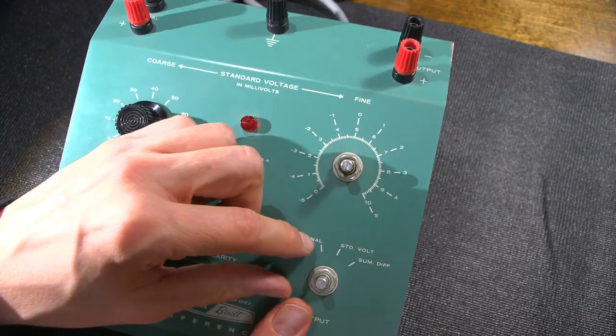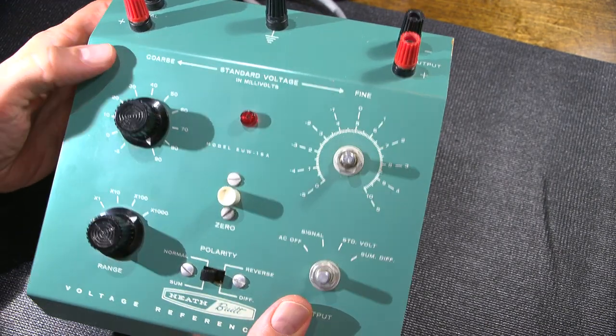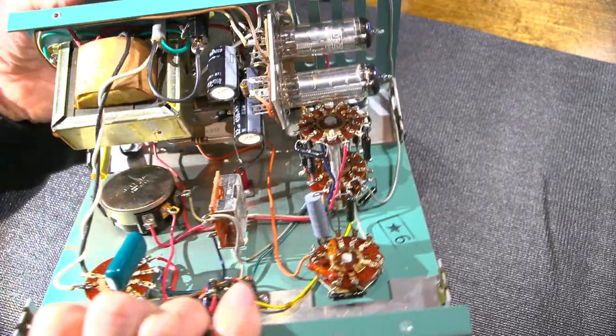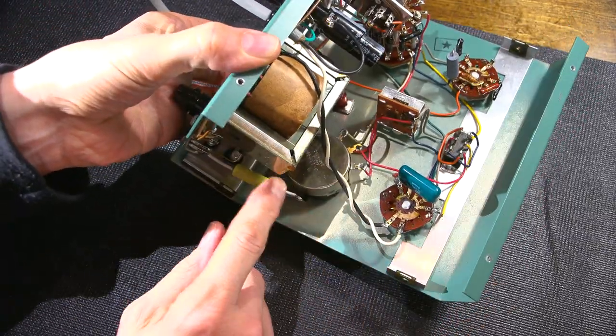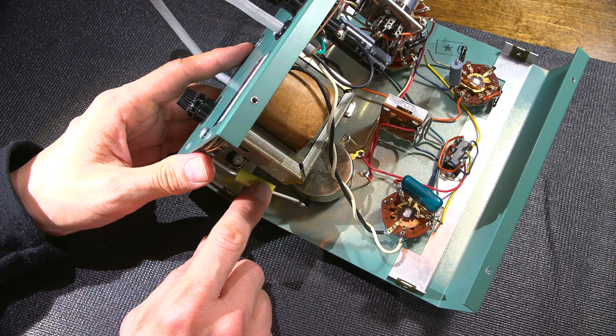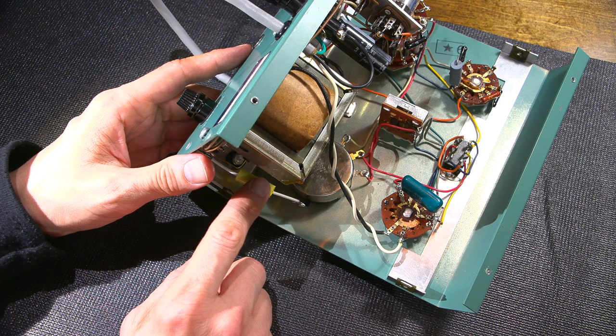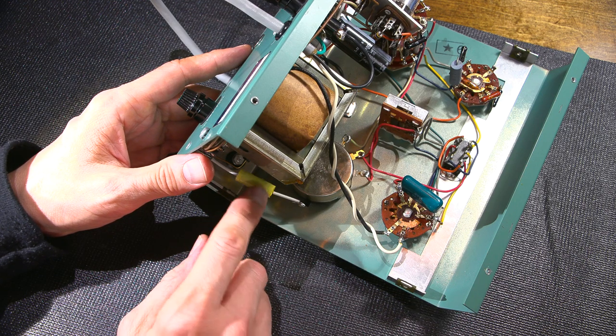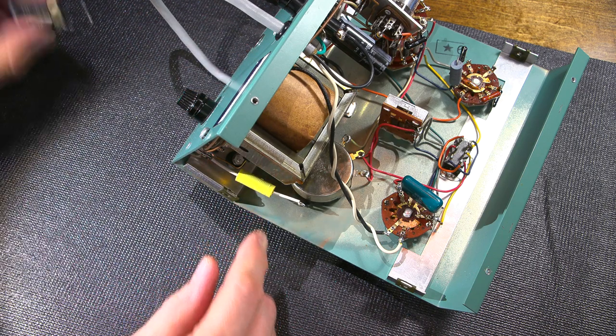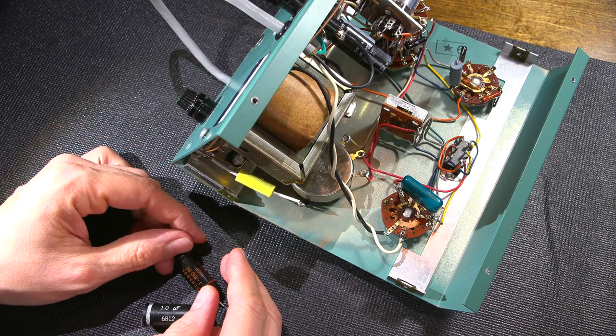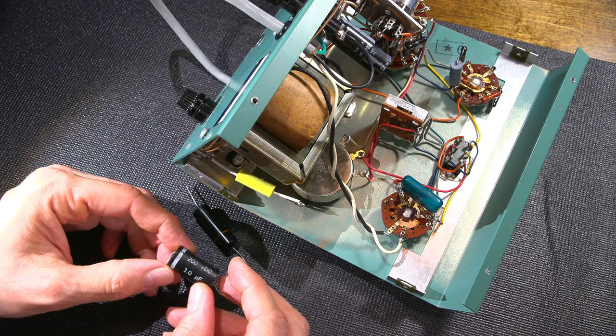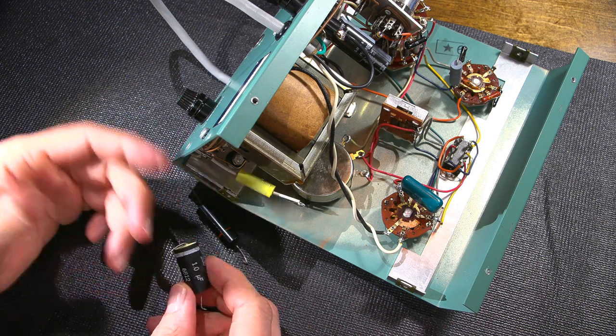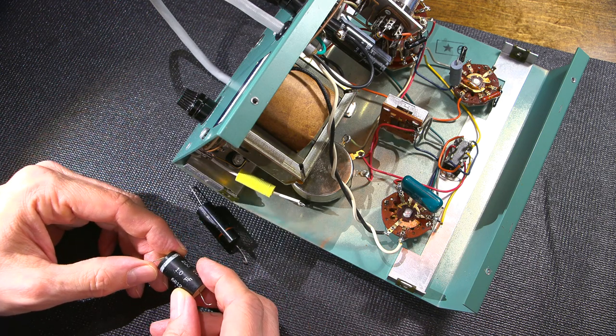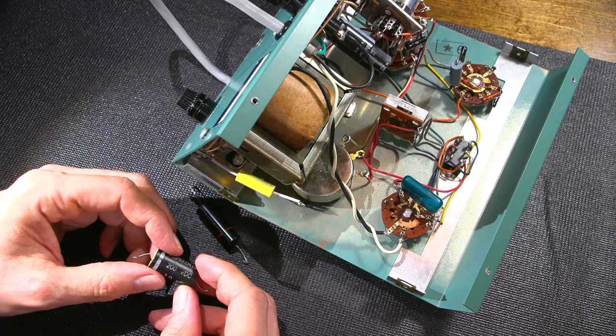Hopefully they're gonna take to the shaft okay. And then we'll attempt to do an alignment. Oh, and I'll also give you an example of the dead film capacitor here. I'll compare a dead film one to a new one and show you the differences over time. And this is the dead film one here that was removed. And this is the other capacitor. This one isn't even worth testing because it's just so bad. You know, sit here for a day and the tester won't even go down.